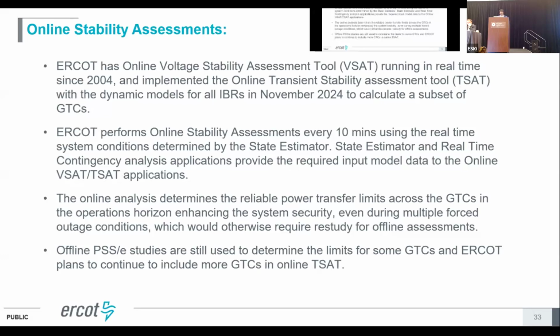And that's where the online stability analysis will help, because it will know exactly what the current system topology is, and it can run those assessments and tell us exactly what our safe transfer limit is across the interfaces. And they determine the flow that we have to maintain in the base case to have an N-1 secure condition. And that's what we use.